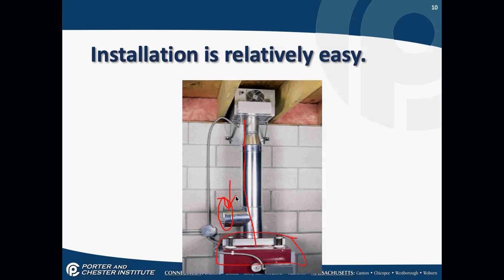That's the barometric draft damper. That's the one with the little swinging door and the weight that I said you have to adjust if the draft is too high or too low. So just because there's a power venter on here doesn't mean we still don't have to adjust draft. What this does, if the draft is too high in the boiler or furnace, this allows air to come in, and air mixes in here and reduces the draft over the furnace. So again, if there's too much draft, we let basement air mix in here, and it reduces the draft.